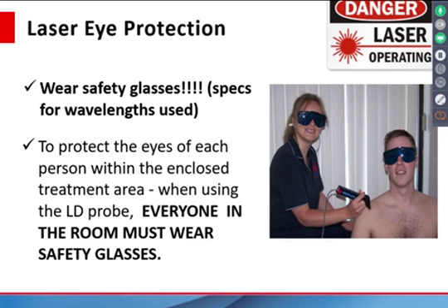So our equipment, we use 660 nanometers and 830 and 840 nanometers of laser light. That means you need to make sure that the glasses you're wearing to protect your eyes protect against those specific wavelengths. Remember that everyone in the room where the laser is being used should be wearing the safety glasses. So if you have a patient with a family member, a child or what have you, they should also be wearing eyewear when the laser probe is being used. Or probably what's even better is ask those people to leave that area during the laser probe portion of the treatment.